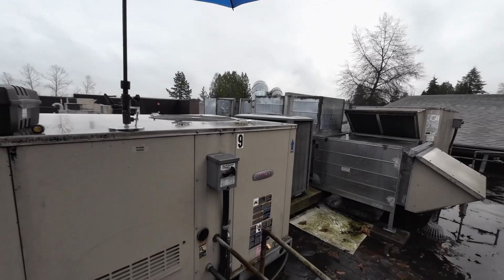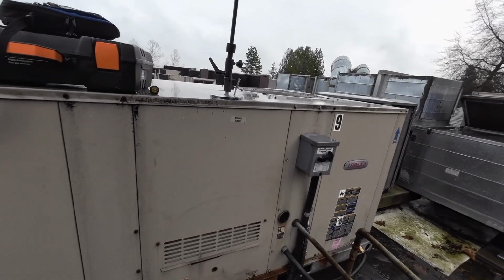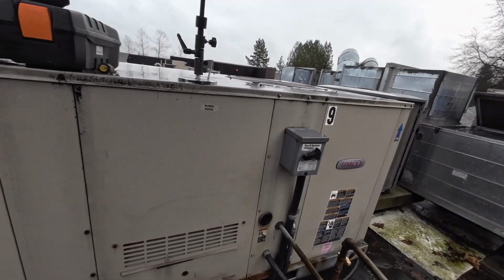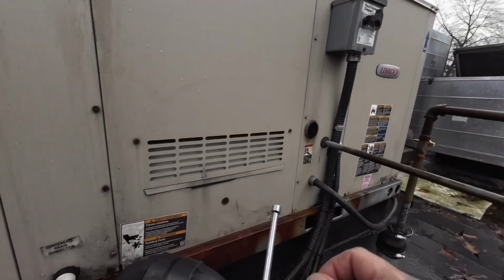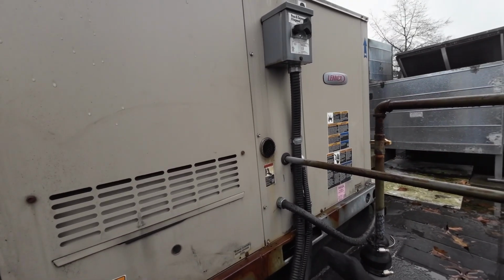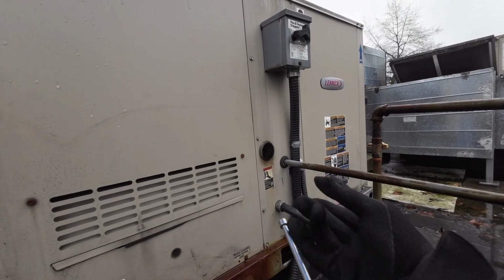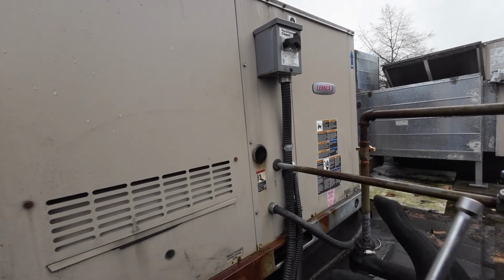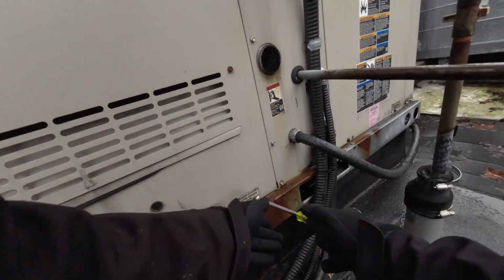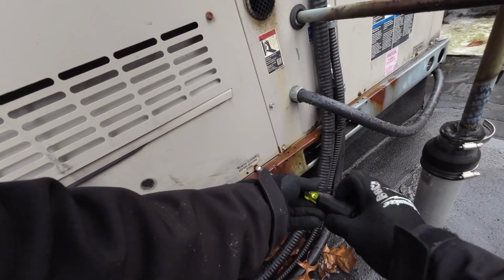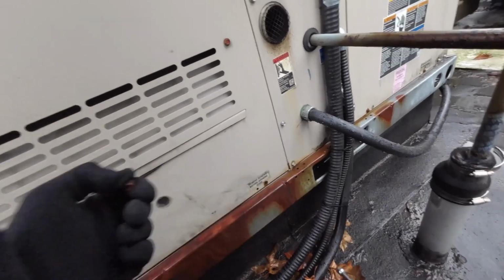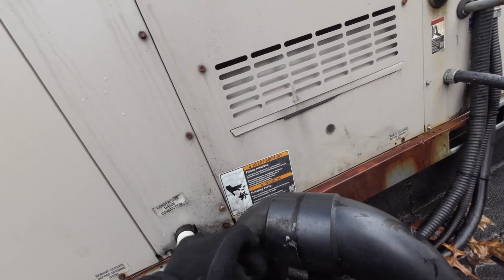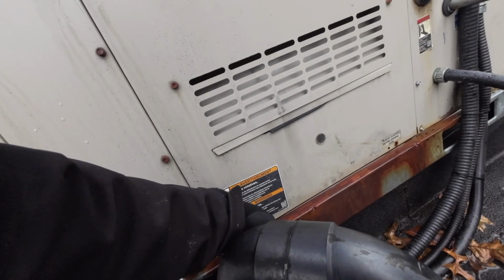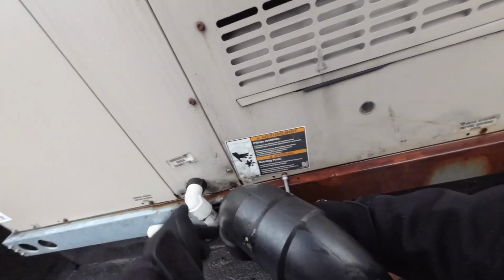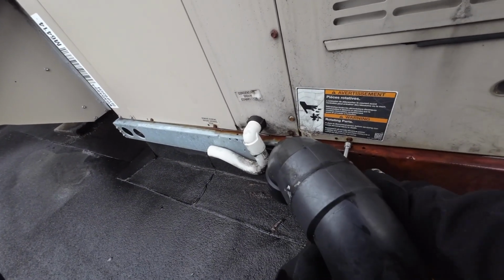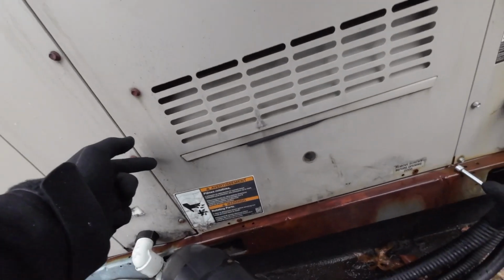So this one over here is smelling really bad, and the air flows from this unit here. It's going over to that economizer over there, which is going right into an office, and they smell it. They smell gas. So let's find out what's going on here. A couple things we're gonna do right off the bat is we're gonna check the gas pressures.